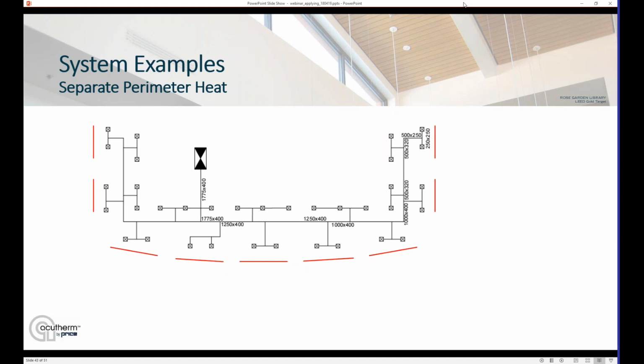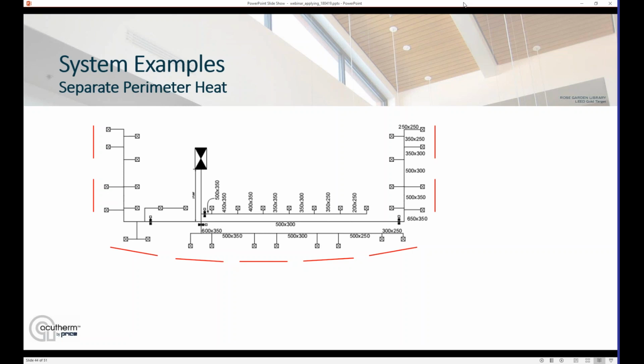And in this particular example, the customer told us they had some tight ceiling restrictions. So we also laid it out as a part medium pressure, part low pressure, whereby we've got multiple zones per floor, modulating volume dampers to control the pressure in each space, and then those medium pressure sections of duct to distribute the air around the floor.